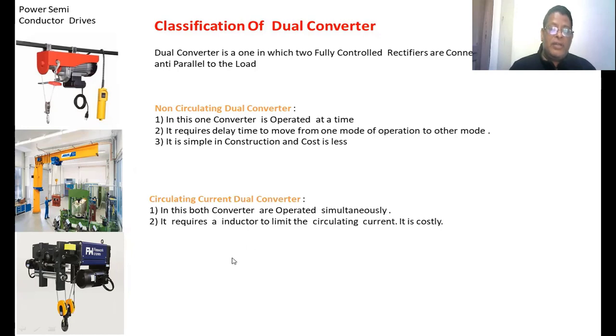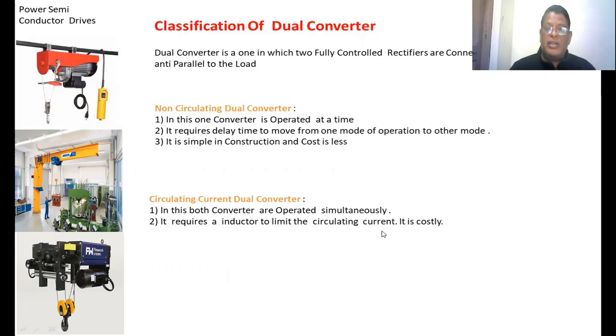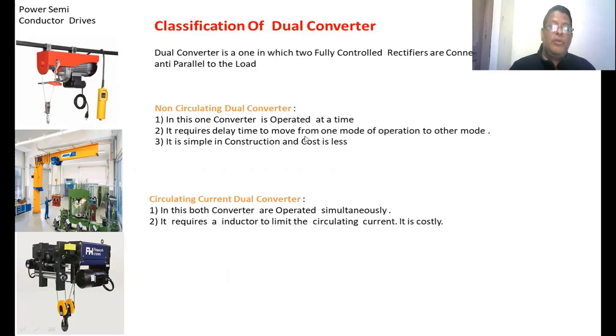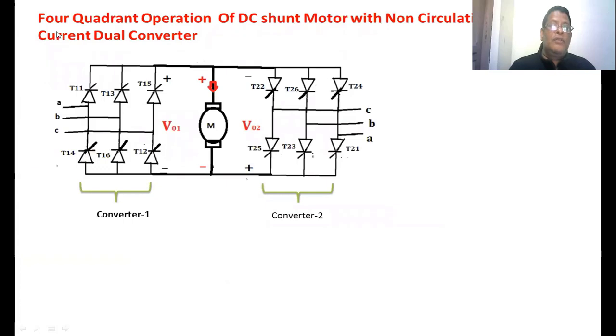The second type is the circulating current dual converter, where both converters operate simultaneously. It requires an inductor to limit the circulating current, making it a more complex and costly circuit. We will first examine the non-circulating dual converter, and then the circulating current dual converter.